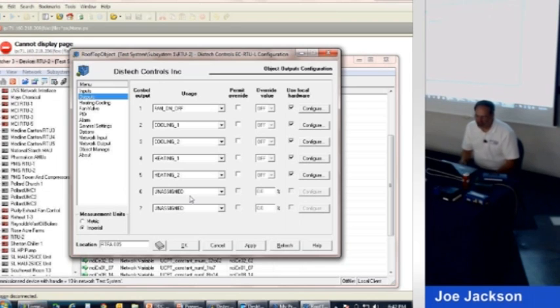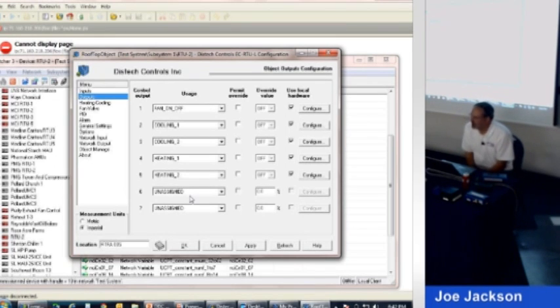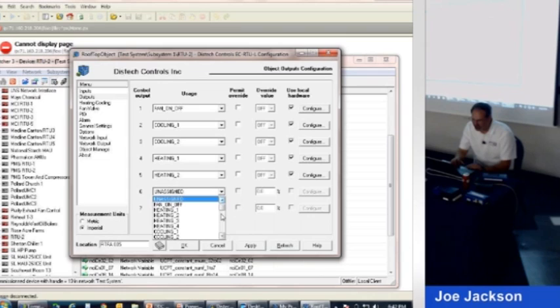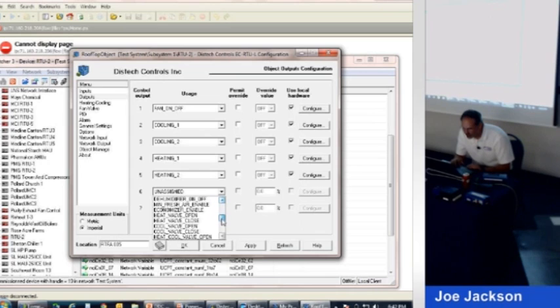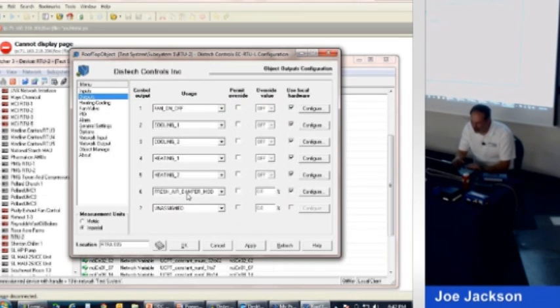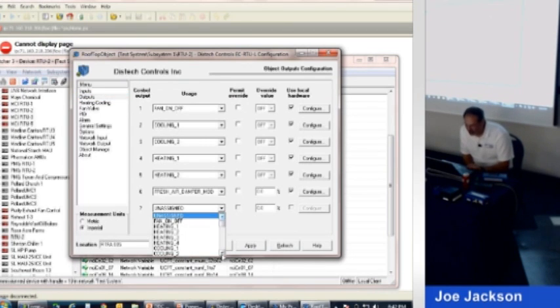But let's say we do want to control the outside air damper. Most rooftops today it's built in, but again, they call it a rooftop controller, but it does a great job of controlling small air handlers, even with chill water and hot water. It'll handle the modulated valves and everything else. But for our sake, we'll just go ahead and act like we're going to hook an outside air damper to it. Fresh air damper modulating. And just because we can, we got one more thing we could turn on and off. Let's see if we can find something interesting for our unit to control. We'll add a humidifier to it.